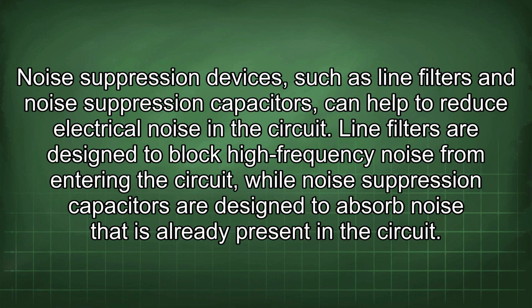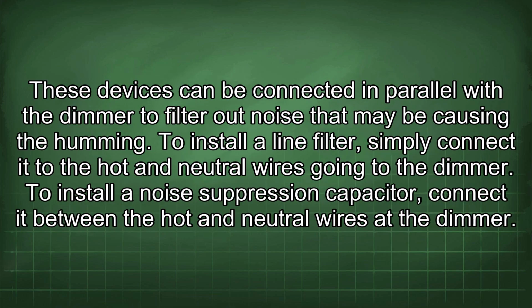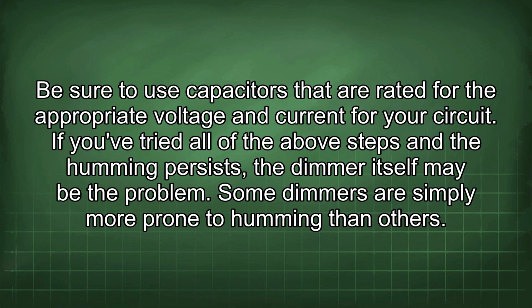Noise suppression devices such as line filters and noise suppression capacitors can help to reduce electrical noise in the circuit. Line filters are designed to block high-frequency noise from entering the circuit, while noise suppression capacitors are designed to absorb noise that is already present in the circuit. These devices can be connected in parallel with the dimmer to filter out noise that may be causing the humming. To install a line filter, simply connect it to the hot and neutral wires going to the dimmer. To install a noise suppression capacitor, connect it between the hot and neutral wires at the dimmer. Be sure to use capacitors that are rated for the appropriate voltage and current for your circuit.